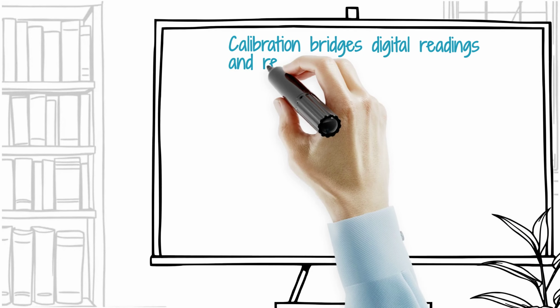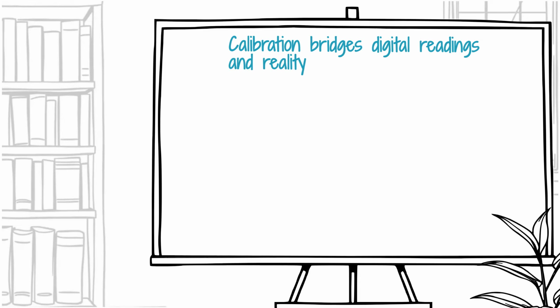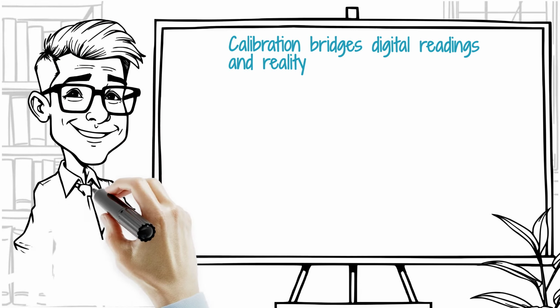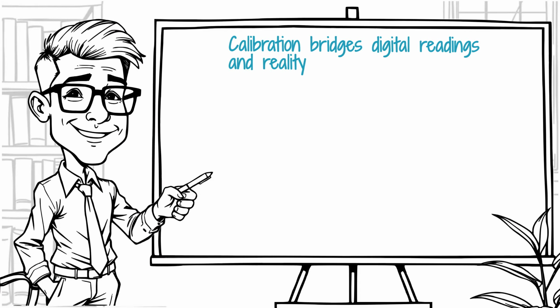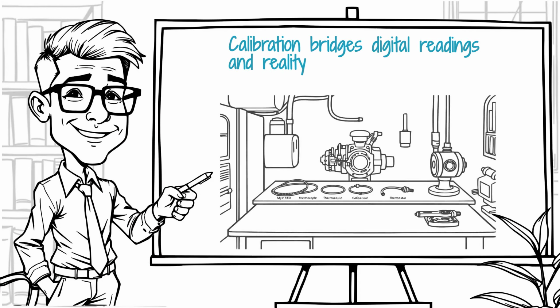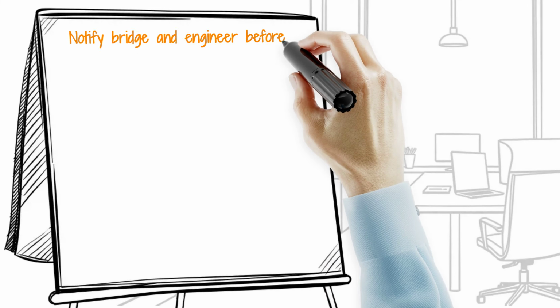Calibrating these instruments is a precise task that bridges the gap between digital readings and physical reality. Before starting any calibration work, ensure you have identified the specific sensor type, whether it is a resistance temperature detector, known as an RTD, a thermocouple, or a mechanical capillary thermostat.